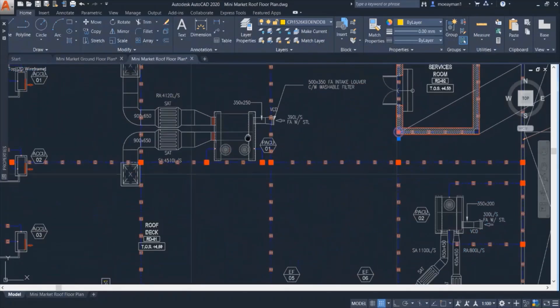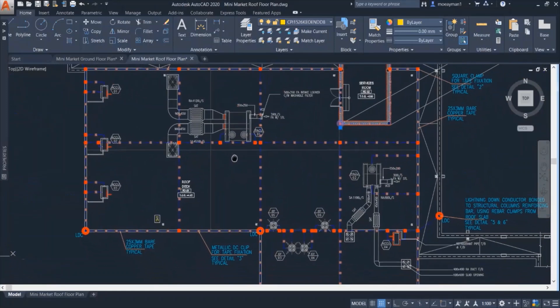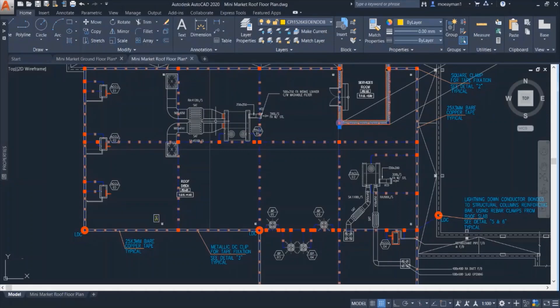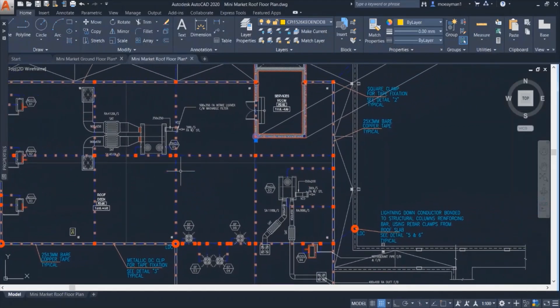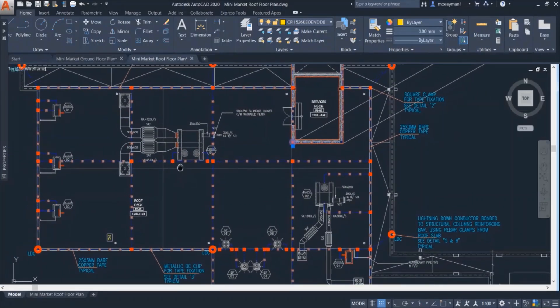Also we can see here on the top of this roof a lot of mechanical equipment or outdoor units. These could be outdoor units for the air conditioning system, extraction fans and etc. Regardless of the type of the outdoor unit it shall be bonded to the lightning network for safety.